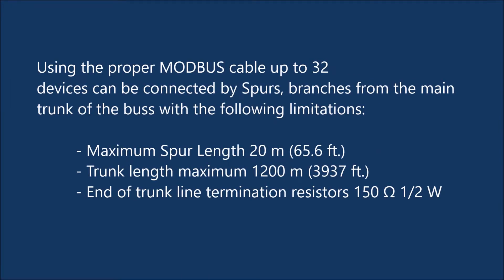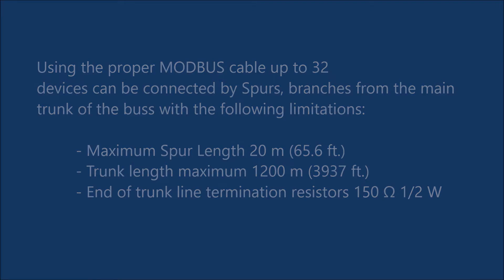Using the proper Modbus cable, up to 32 devices can be connected by spurs — branches from the main trunk of the bus — with the following limitations: maximum spur length 20 meters (65.6 feet), trunk length maximum 1,200 meters (3,937 feet), and end-of-trunk line termination resistors of 150 ohms at 1/2 Watt.